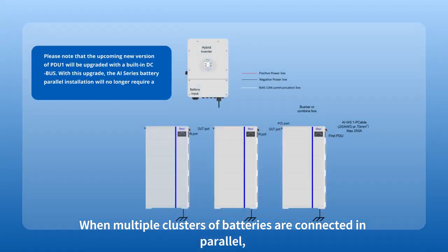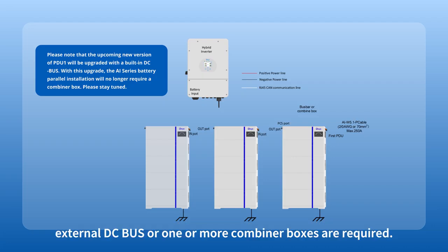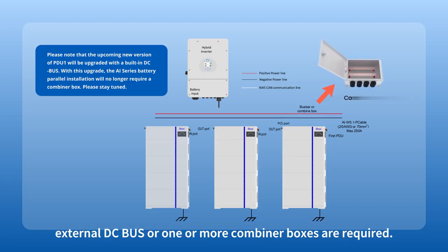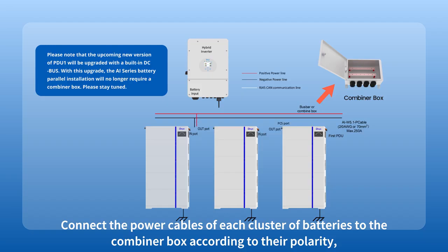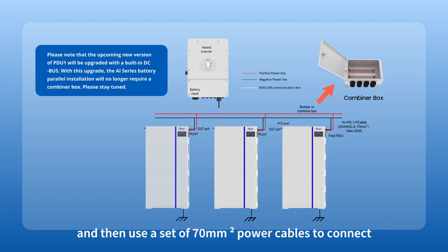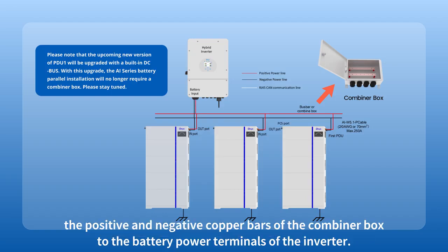When multiple clusters of batteries are connected in parallel, external DC bus or one or more combiner boxes are required. Connect the power cables of each cluster of batteries to the combiner box according to their polarity, and then use a set of 70 mm squared power cables to connect the positive and negative copper bars of the combiner box to the battery power terminals of the inverter.